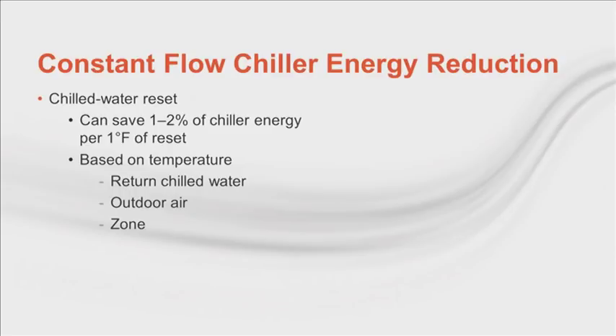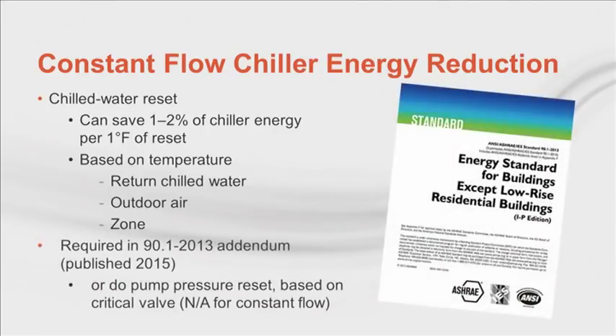Resetting the chilled water temperature set point upward at part load conditions can save 1 to 2% of the chiller energy per degree of reset. Most of today's chillers have the option for chilled water reset built right into the controller. You simply add an outside air or return water temperature sensor and enter a reset ratio. The amount of savings you can get changes based on the chiller type and whether or not it has a variable frequency drive. And let's not forget ASHRAE 90.1.